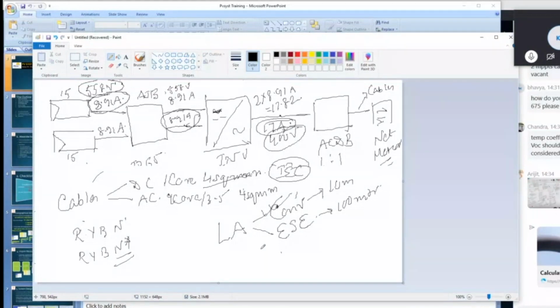Lastly is grounding. We need to ground the DC and AC, and make an LA grounding. Generally, DC1, AC1 and LA1 is enough. Tender wise, it can be DC2, AC1 and LA1. What is grounding? Whenever we take a GI strip or a cable from the structure, it is to ensure there is no leakage current, and we ground it through an electrode.